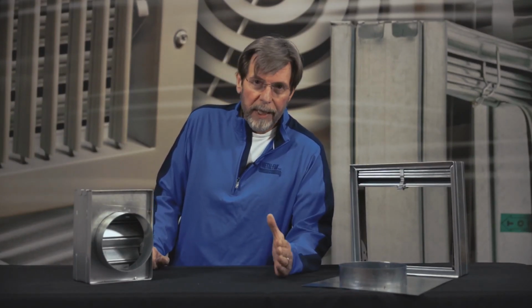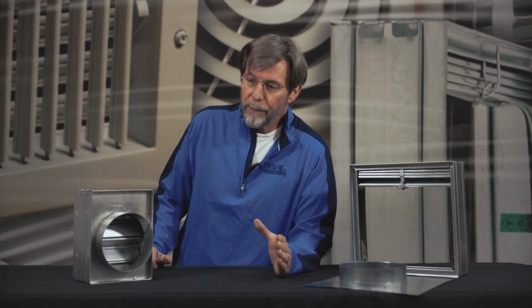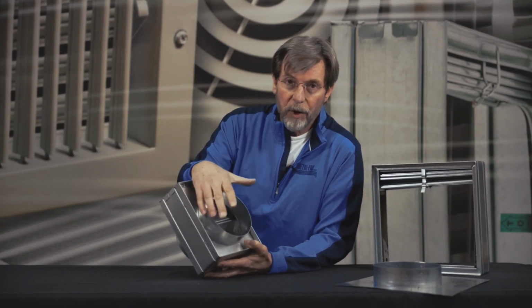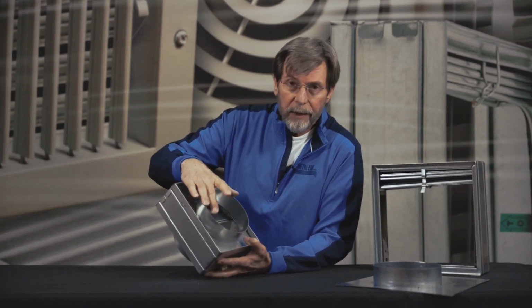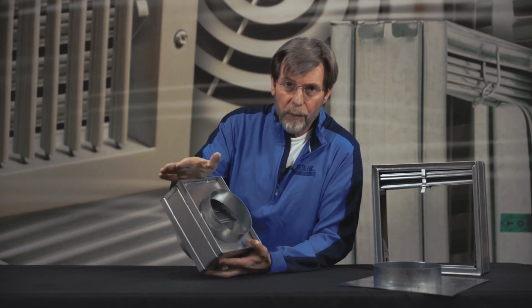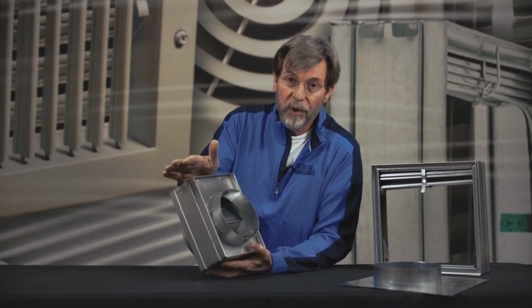Now let's take a closer look at our type C damper. So when we're looking at the type B dampers, we saw that it had a B channel in it, and the type C dampers are going to have even less airflow restriction than a type B. This is type C. It's going to have a transition plate, going to have a duct connection collar. We make these where you can get this collar in an oval shape or a square rectangular shape. They're still going to be type C dampers. We're just going to match it up to the duct that's being installed on the project.